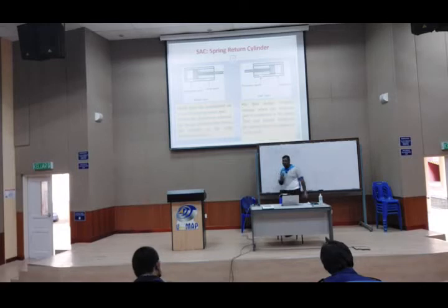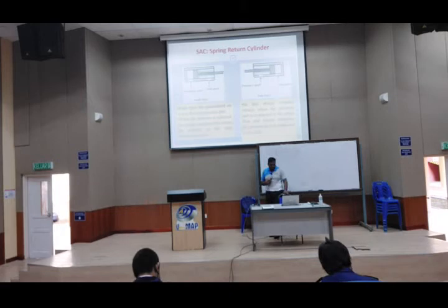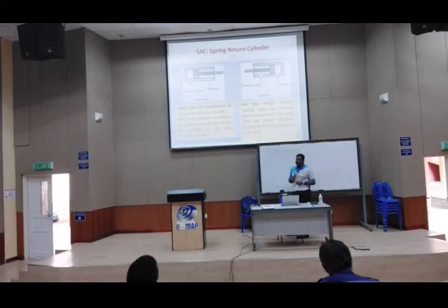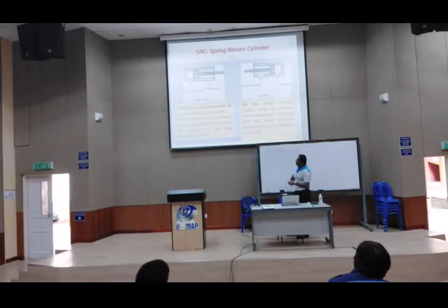Okay, so for the normal single acting cylinder, you have two types. One is push type, the other is pull type. So what is the difference? You can see here. The difference is in the construction. This is a normal port like before, so air is entering here. You have two places. One side has a spring, and the other side is empty. The compressed air is entering and it will push, and your piston will move up. For push type of single acting cylinder, your cylinder will go out. When air enters, the piston goes out.